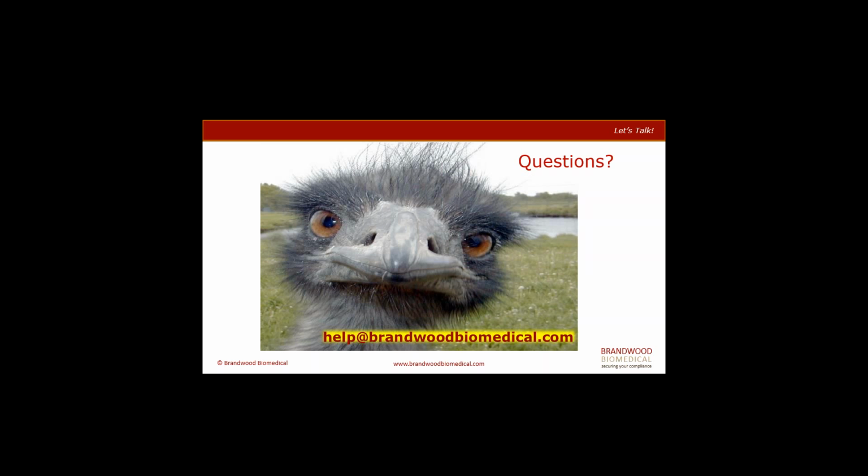Another question I have here from Chayapon, I apologise, I'll try and pronounce Nagosapura. Risk management is part of DHF. Do we need a separate risk management file? Some trainer mentioned that we need separated. Yes, it is part of the DHF, but the risk management file is a living document and should be maintained separately.